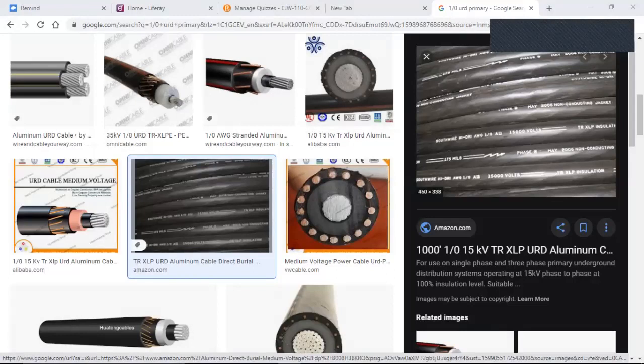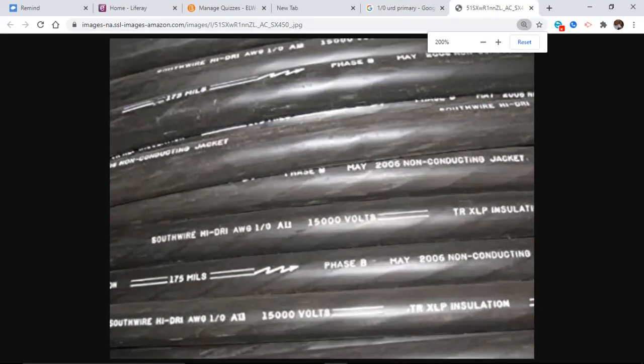Let's share screen. This is a reel of underground primary. I don't like the way they got this one shown here. First, it's going to show you the wire size, the voltage rating on it. I don't know if it's going to show in this area, but it is stamped on it. There's footage marks on the wire, that's for all conductor except bare conductor, you can't put a footage mark on that. All covered or insulated conductors have a footage mark on it, so you're able to tell how many feet you're pulling out.